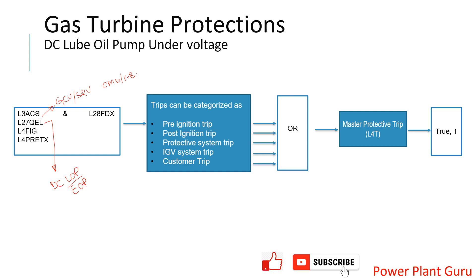EOP is very much essential for safe shutdown and machine safety. If there is any problem in the AOP or main oil pump, then EOP is required for safe shutdown. That is why, before startup, the control system checks whether this system is healthy or not. It takes an I/O from GT MCC and checks whether there is an under-voltage or not. If voltage is satisfactory, it gives a healthy signal. If under-voltage is found, this bit becomes active, and since L28FDX indicates no flame, both the under-voltage of GT MCC for EOP feeder and flame not detected become part of this pre-ignition trip.